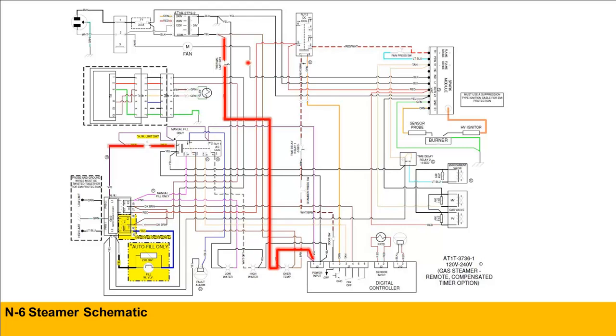Now, on the overtemp, once again, a safety overtemp, the alarm will sound and the overtemp light will illuminate. So we've got the light, and here's our switch in the diagram as a whole. As you can see, the switch itself is in line with the power going to the main control board. So with the high water and the overtemp, you will not see a display. It will just be in an overtemp condition. With the high water and the overtemp, these alarms will occur with the unit plugged in, and obviously not turned on.